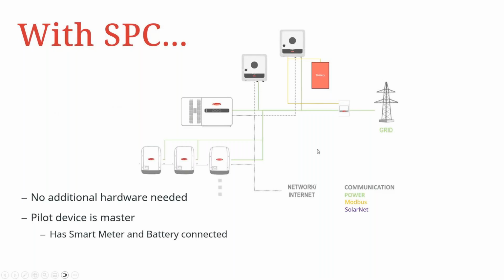But then with the SPC, it is now possible to have seamless control of these components inside one unit. The only thing to add here is that if there is going to be a Gen24 Plus in the system, please ensure that the inverter connected to the battery, the Gen24 Plus inverter, is the master of this particular system in terms of communication. Once that is done, then you don't have a problem - it's a seamless connection.